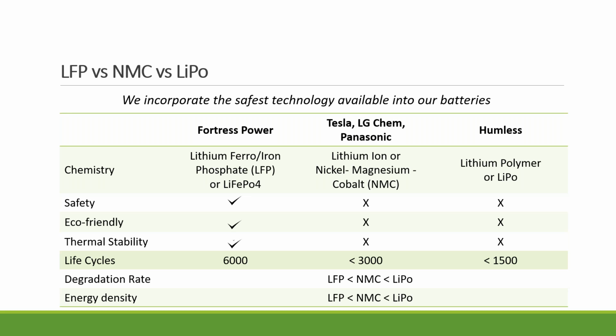Why do we choose lithium iron phosphate, or LiFePO4? It's the same product we talk about. It's safe because it does not have cobalt. Cobalt is a very temperature-volatile element. So if you operate outside of that window, and the BMS does not shut it off, then you have a likelihood of thermal runaway or even catching fire.